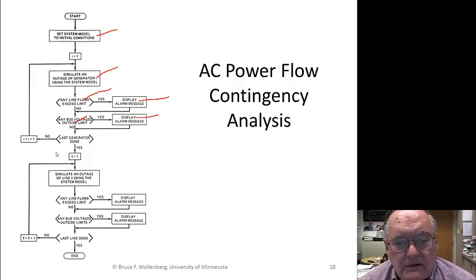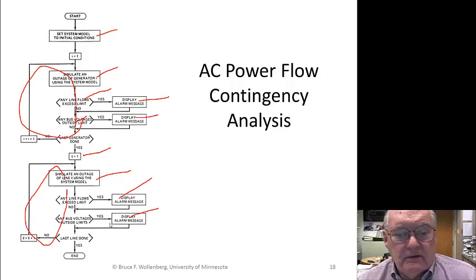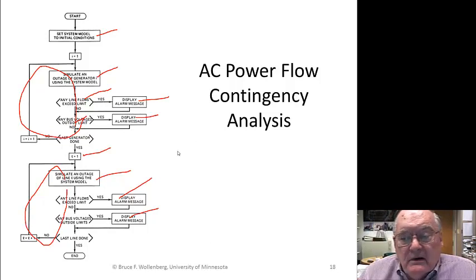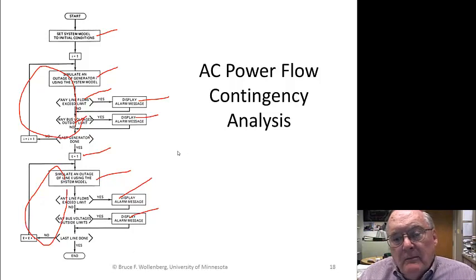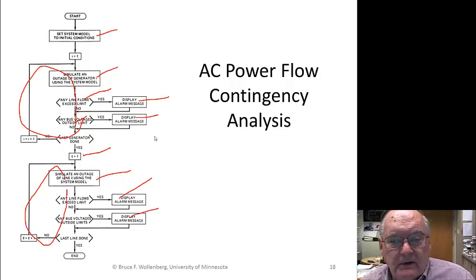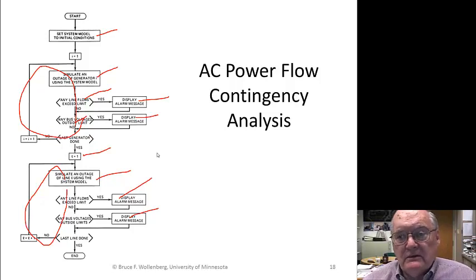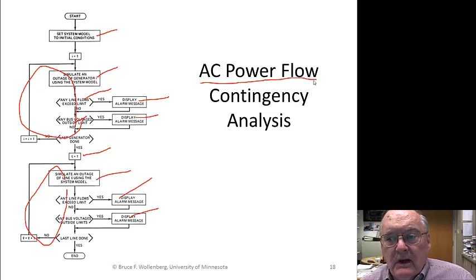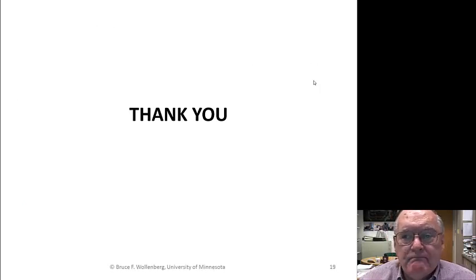Then go back and do all the other generators. Then do all the lines. We simulate an outage of line L, etc. Any alarm messages for overloads and voltage limits, and we do all the lines. So we loop through all the generators. We loop through all of the transmission lines. It's an exhaustive procedure, especially when we're doing it with AC. Now, many people say, well, you can use the linear power flow. If I use the linear power flow, I lose all information about the bus voltages, so that we can't operate the system that way. So AC power flow is ultimately the choice that you're going to make if there's any concern about voltage magnitudes, reactive effects. Thank you very much.